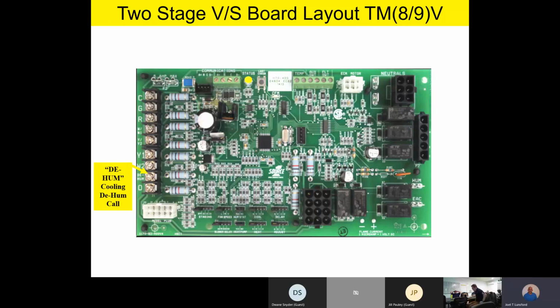So be sure if you want to have extra dehumidification, you select that humidistat yes jumper. And just remember that you have to have a humidistat on that dehum terminal, between dehum and R terminal, 24 volt hot. Otherwise, if you have the jumper in the yes position and you don't use this, your fan will never get above 80% airflow. So this is really important during your startup and commissioning: if you're not going to use this, make sure your humidistat jumper is in the no position. And again, we'll show you that jumper a little bit later on when we start setting up our airflow.